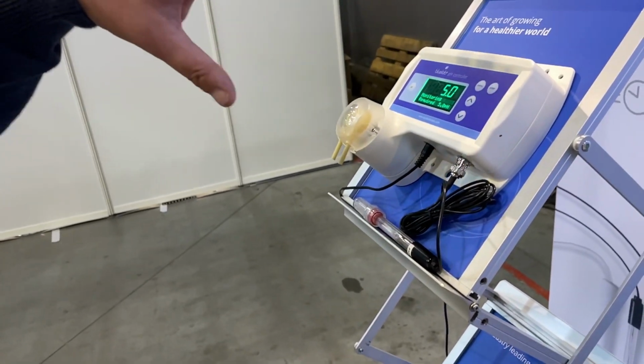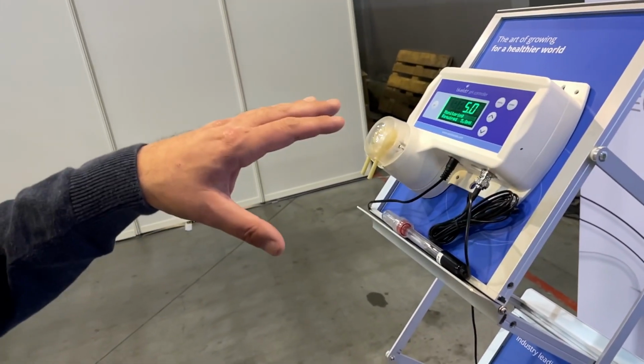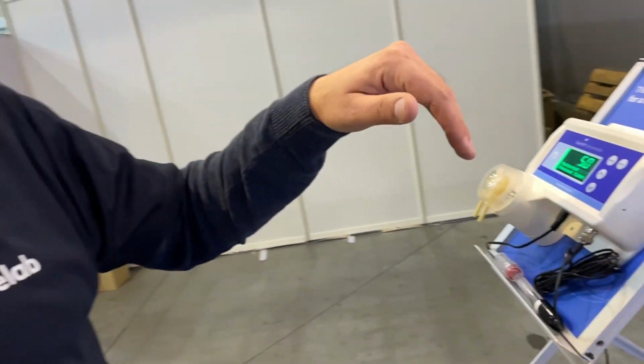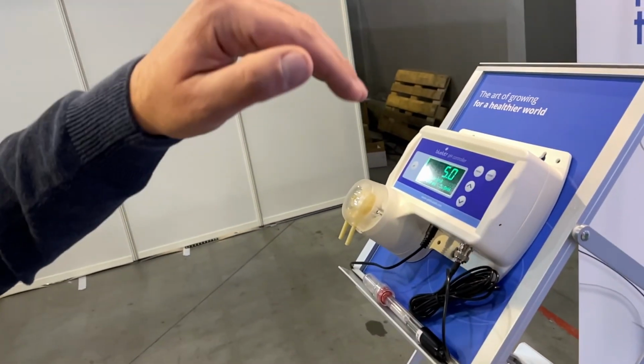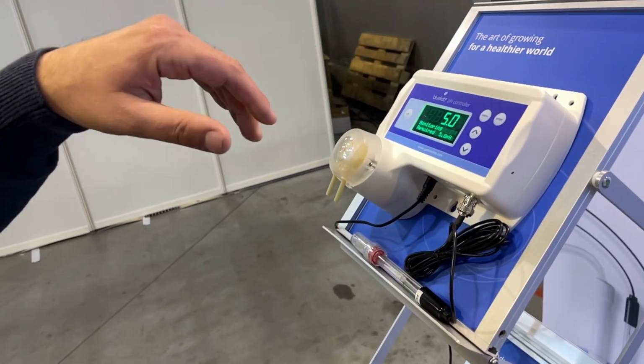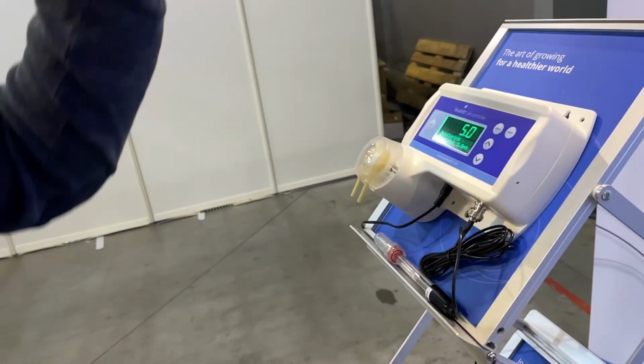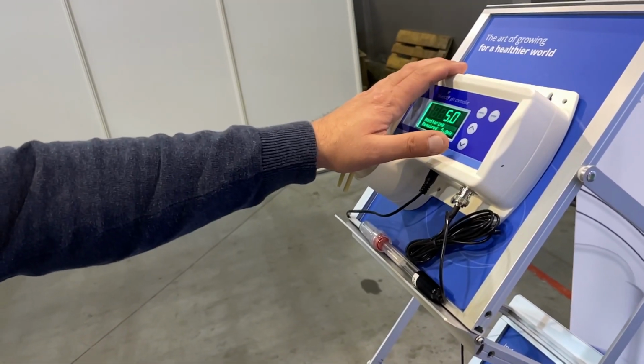The way this differs from other meters out there - lots of meters will dose nutrient or pH until the correct level is met. But the problem is once the sensor says okay, the pH is now correct, 5.8, you've been adding in acid, by the time that tank mixes and homogenizes, usually the pH will drop further or the nutrient will increase further. So what this does is you set an on time, when it doses, and an off time, which allows it to mix. So it measures, doses, mixes - measures, doses, mixes - so you never overshoot if you set it up correctly.